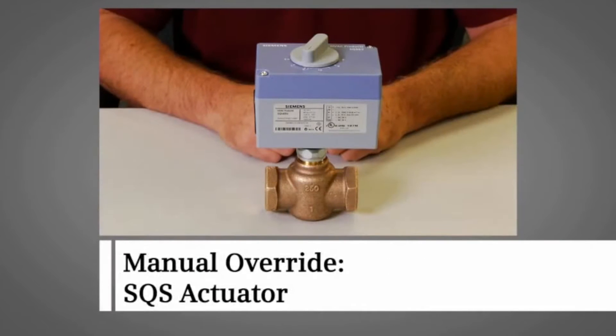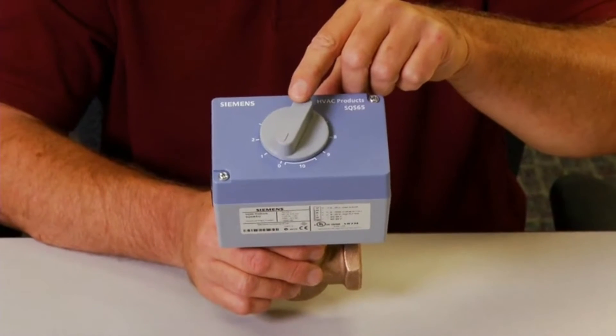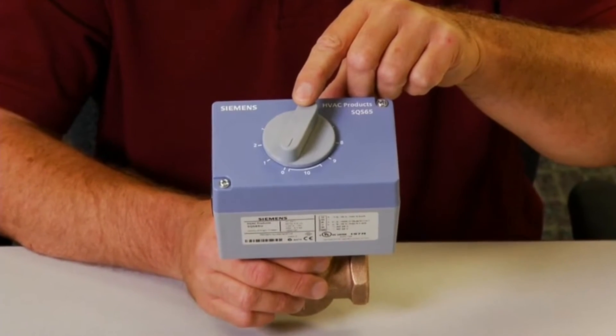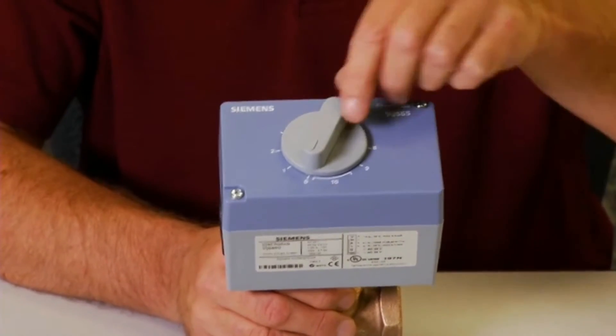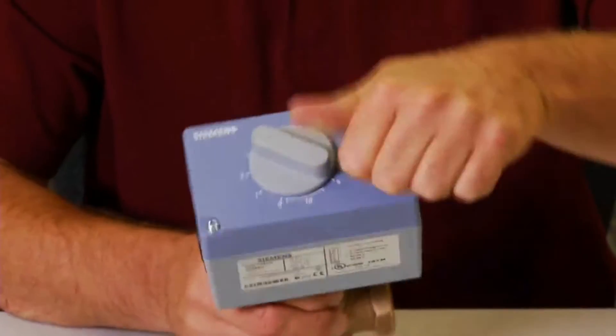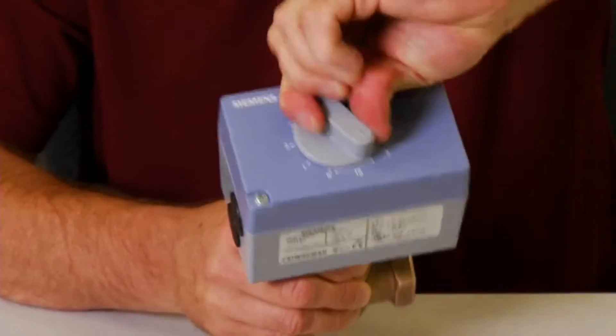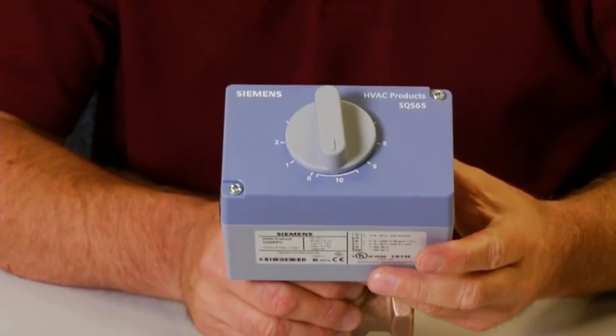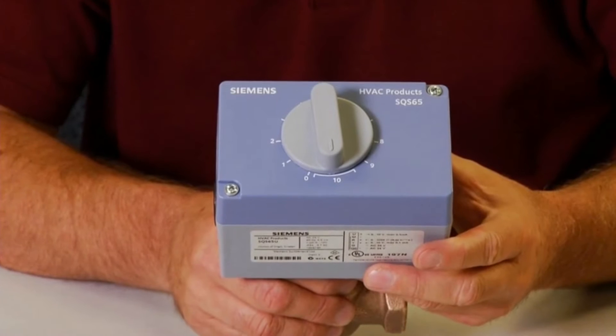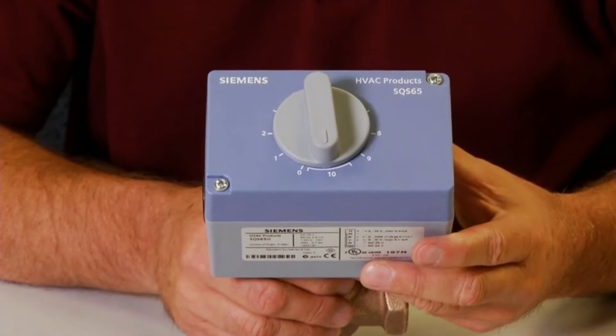For the SQS actuator, the manual override allows us to manually open or close the valve as needed when power or a control signal is not present. By turning the manual positioning knob, we can position the actuator to any position between 0 and 10. The actuator will hold its manual set position until a control signal is received. A control signal takes priority over any set manual position.